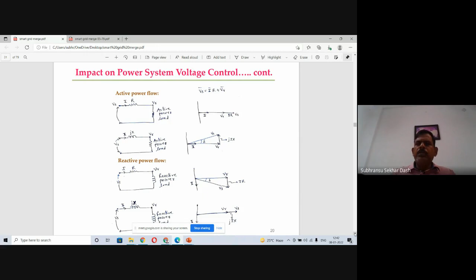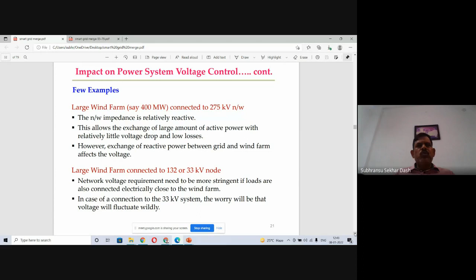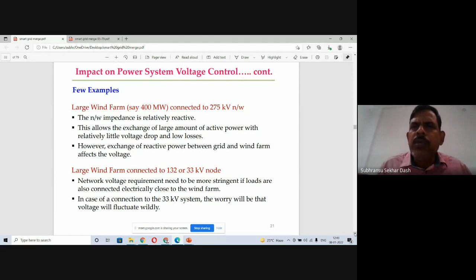Now a few examples. Large wind farms, say 400 megawatts, connected to 275 kV networks. The network impedance is relatively reactive. This allows the exchange of a large amount of active power with relatively little voltage drop and low losses. However, exchange of reactive power between grid and wind farm affects the voltage. A large wind farm connected to 132 or 33 kV nodes: network voltage requirements need to be more stringent if loads are also connected electrically close to the wind farm. In case of connection to a 33 kV system, the worry will be that voltage will fluctuate wildly.